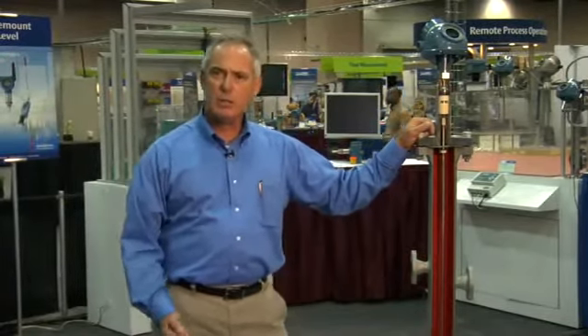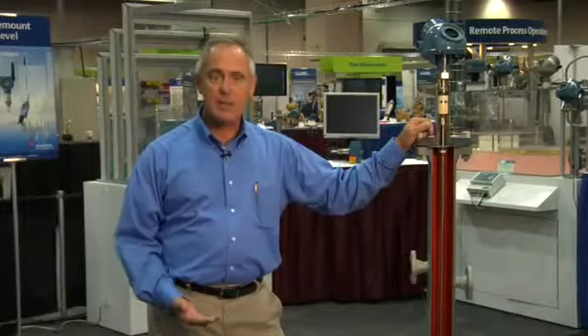A lot of our customers talk to us about the difficulties they experience in measuring level in high-pressure saturated steam vessels, such as boilers or feed water heaters. A lot of the traditional products used to measure level in these devices are density-based. And as you know, density can actually vary substantially from ambient conditions to full-bore run rates, up to maybe 30%. So that makes these devices hard to use to measure level.